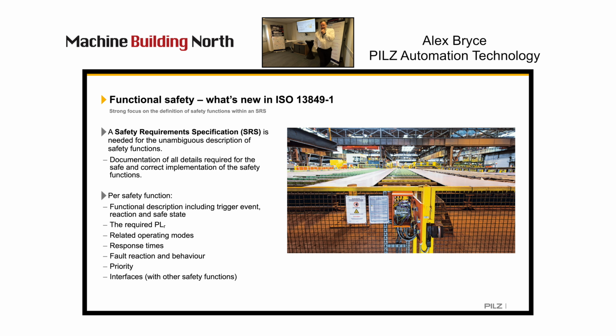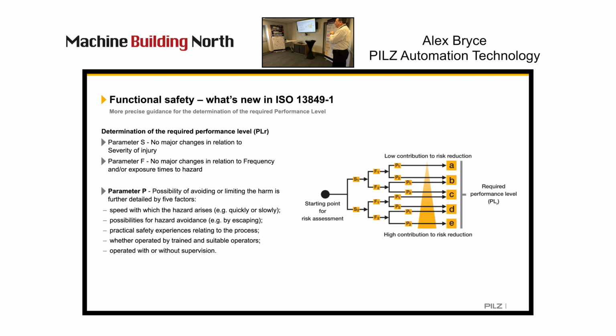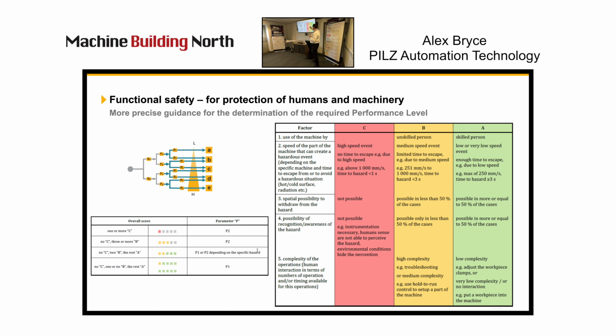The other thing that's changed, anybody familiar with safety control systems will know that chart. The parameter P, the possibility of avoiding the issue, was always about whether it's fast or slow moving, but it was never exactly defined. The new version gives us a definition and questions we can ask: use of machine, speed, spatial areas, possibility of avoidance, trained personnel, and so on. We choose A, B or C, and a chart tells us if we have one or more C's then it's P2, or whatever combination puts us into 1. So we get more definitive control over the performance levels we need to design the system to.